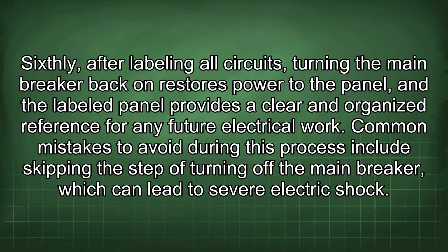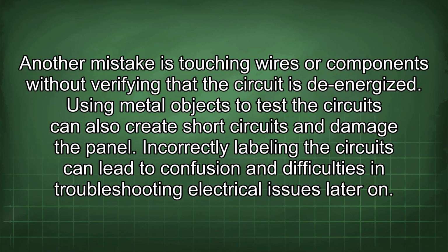Common mistakes to avoid during this process include skipping the step of turning off the main breaker, which can lead to severe electric shock. Another mistake is touching wires or components without verifying that the circuit is de-energized. Using metal objects to test the circuits can also create short circuits and damage the panel. Incorrectly labeling the circuits can lead to confusion and difficulties in troubleshooting electrical issues later on.